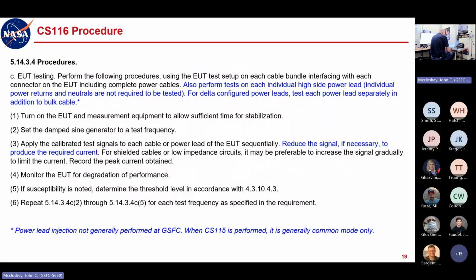And so a few notes from their procedure. Once again, it says also perform tests on each individual high side power lead. Individual power returns and neutrals are not required to be tested. So when we apply CS116, we generally only apply it as a common mode type of test. Certainly nothing is stopping you from applying it on an individual power lead, but know that you're probably representing a different type of transient than something that's hitting an entire cable bundle. If it's on a power lead, it's something that's happening on the power bus. So it's probably a different type of transient, and you just want to tailor the limit differently. And if you end up with the same limit, so much the better, but just put the analysis in to make sure that what you're doing is representing that type of transient and not a common mode one.